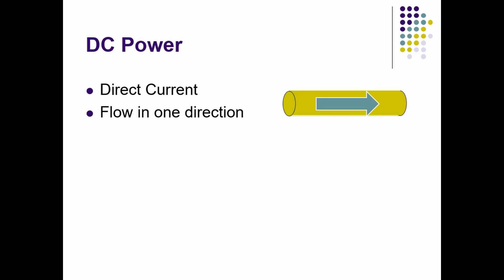To function properly, an X-ray tube requires DC power. In the X-ray tube, we only want the electrons flowing from the cathode to the anode, not the other way.